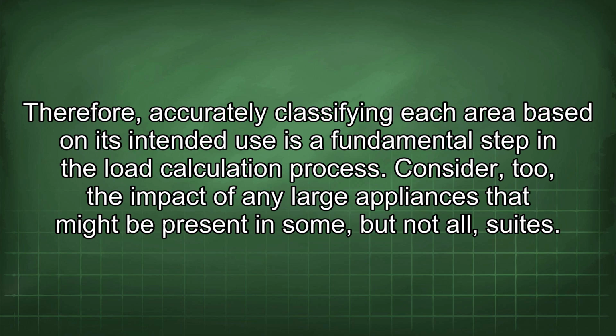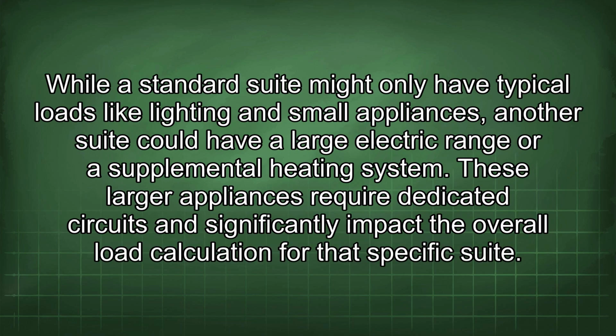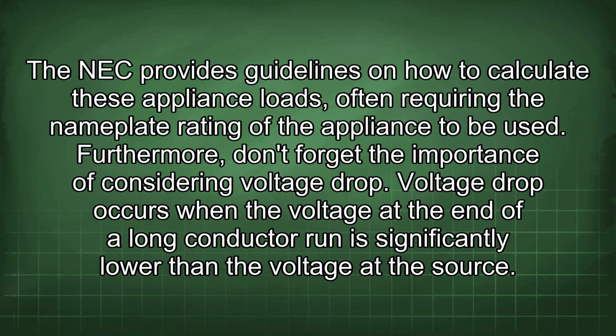Consider, too, the impact of any large appliances that might be present in some, but not all, suites. While a standard suite might only have typical loads like lighting and small appliances, another suite could have a large electric range or supplemental heating system. These larger appliances require dedicated circuits and significantly impact the overall load calculation for that specific suite. The NEC provides guidelines on how to calculate these appliance loads, often requiring the nameplate rating of the appliance to be used. Furthermore, don't forget the importance of considering voltage drop.